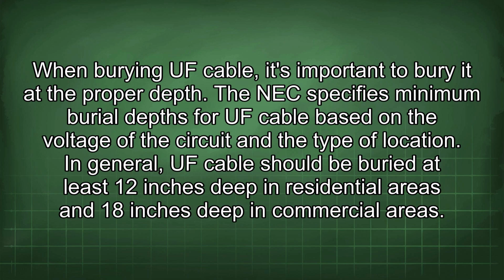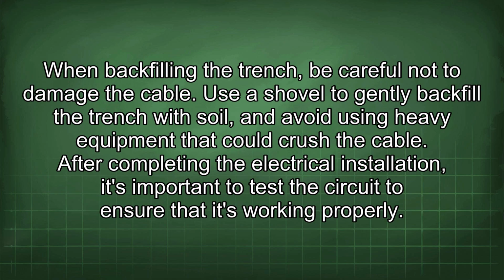When burying a UF cable, it's important to bury it at the proper depth. The NEC specifies minimum burial depths for UF cable based on the voltage of the circuit and the type of location. In general, UF cable should be buried at least 12 inches deep in residential areas and 18 inches deep in commercial areas. When backfilling the trench, be careful not to damage the cable. Use a shovel to gently backfill the trench with soil, and avoid using heavy equipment that could crush the cable.